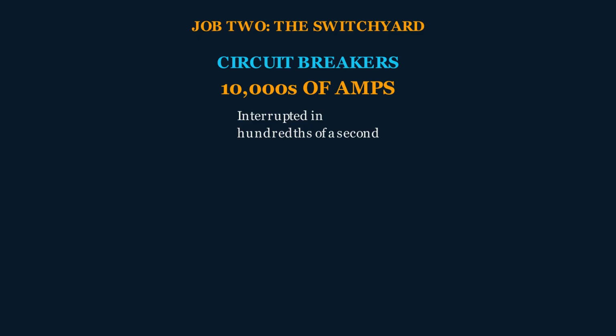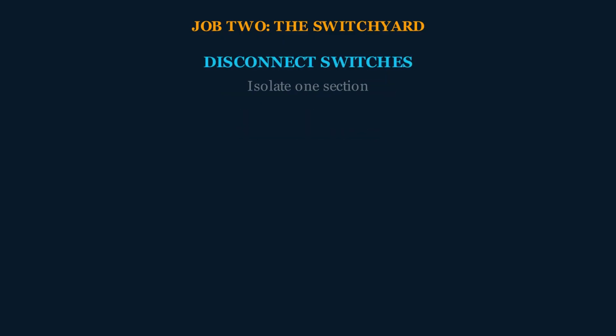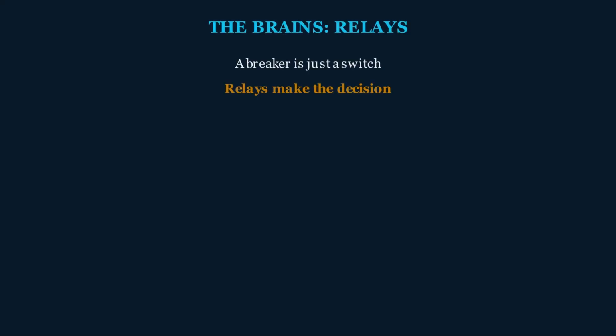All in a few hundredths of a second. And then there are the disconnect switches, the ones you can actually see open, swinging a metal arm up into the air. Those aren't for faults. They're for people. They physically isolate a piece of equipment so a crew can be certain it's dead before they touch it. When a line faults, the breaker opens and isolates just that one section, and the rest of the grid stays lit. Which raises the obvious question.